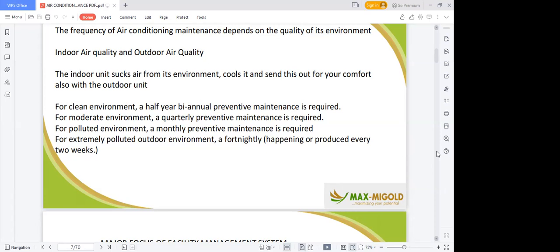So for a clean environment, a half-yearly, biannual preventive maintenance is required. If you are in an environment where the air is good, a biannual preventive maintenance is required. For a moderate environment, quarterly preventive maintenance is required. For a polluted environment, monthly preventive maintenance is required. And for an extremely polluted outdoor environment, maintenance every 2 weeks, a fortnight, might be just sufficient. If you go around Lagos, we cannot get a place that is 100% clean, except some private companies. But most areas and most buildings within Nigeria fall within the moderate environment, which leaves us with quarterly maintenance.